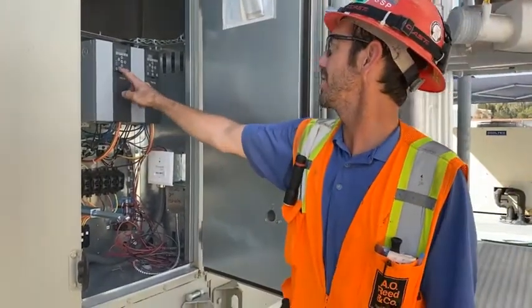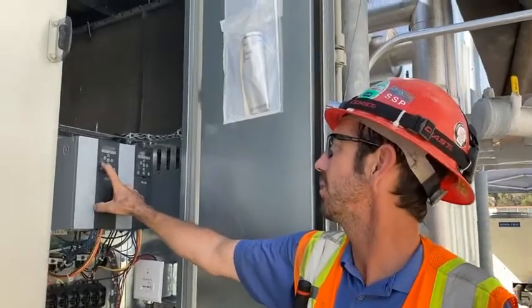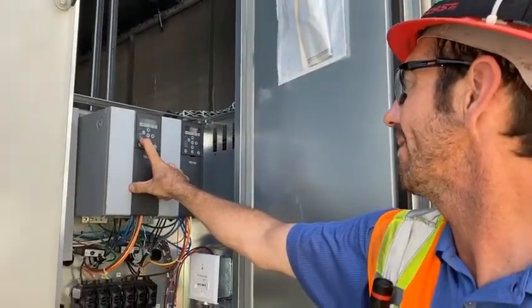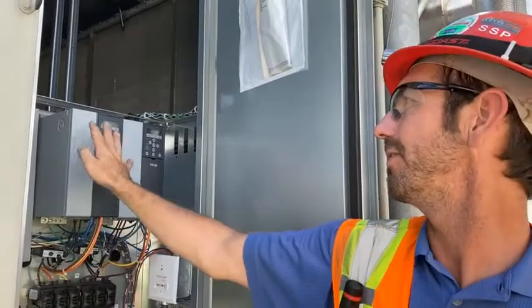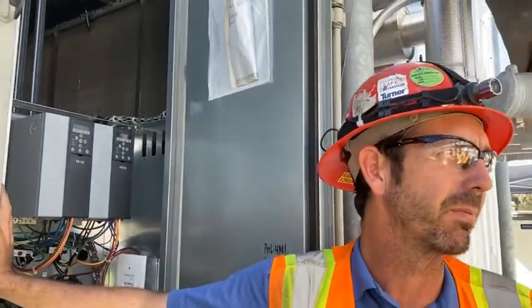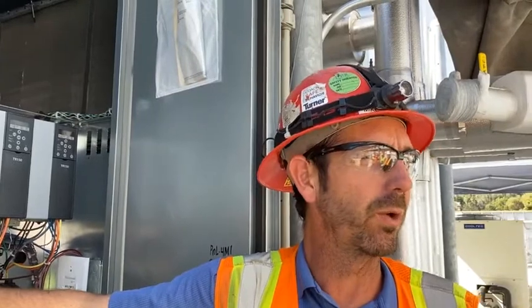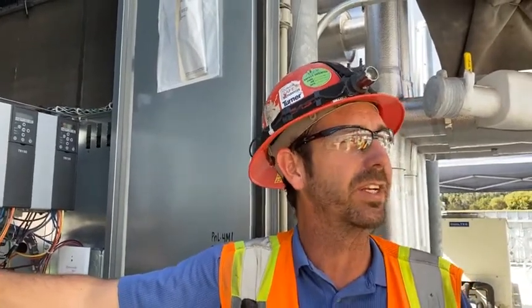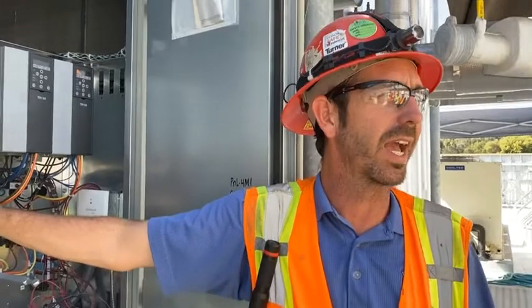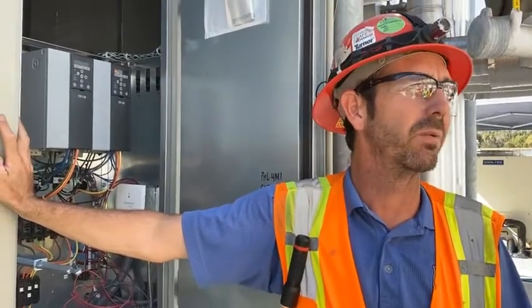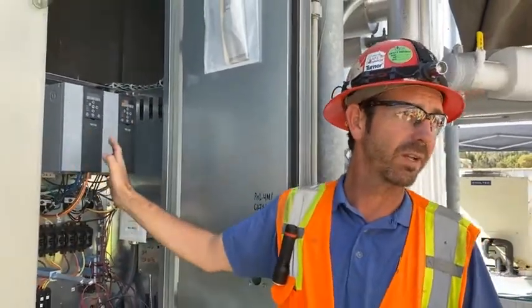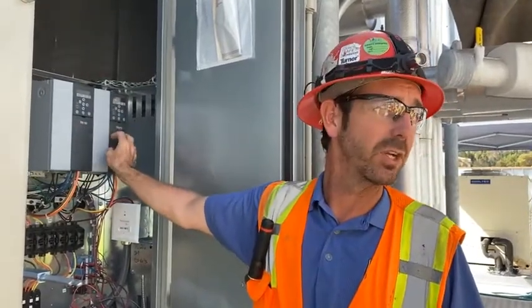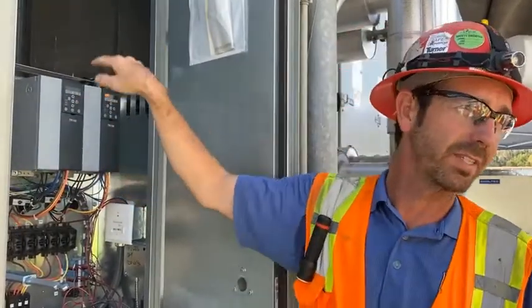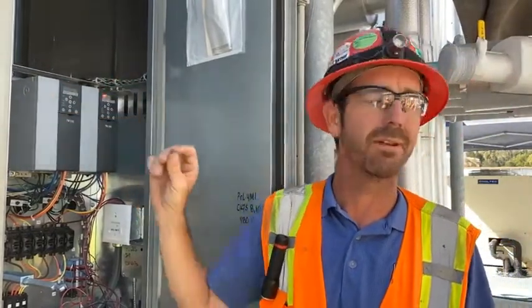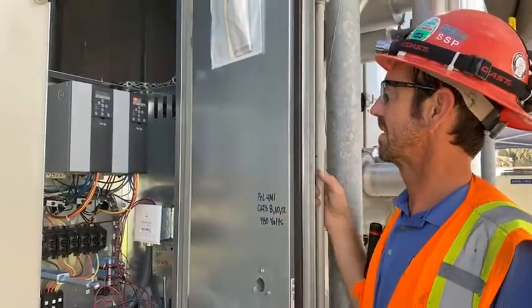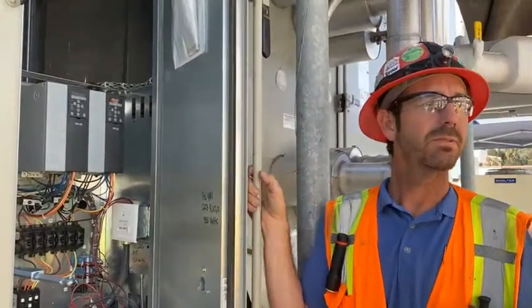If you have an alarm condition, you'll have a red light down here. If it's a warning, it'll be an amberish light right here. If you see that and you see a fault code, we've got to refer back to the book for the proper alarm or warning, okay? A warning won't necessarily shut off the unit. It's just saying, hey, we're getting into a condition that someone needs to look at, okay? An alarm will shut off the unit and it won't work, okay? That specific drive won't work. If you're getting an alarm on one and not the other, the unit can still try to operate, but again, we're going to be short cycling air around the unit, right? Because one's running and one's not. Any questions on this one?